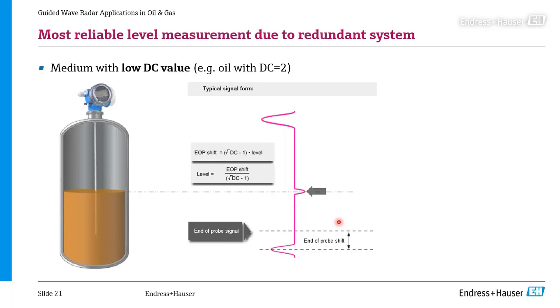Now, this gives me one more thing. This end of probe signal: if you shorten the rod or the rope, you need to tell the unit you did so. Because if you don't, the unit thinks, out of the factory, that the rod has a certain length. So the end of probe signal should be within a certain bandwidth. If you now took, whatever, a foot or 3 feet off, then the end of probe is somewhere else. So you need to tell the unit that you shortened or lengthened the probe. It's only pressing of 2 buttons. Have it determine its own electrical length again. You don't need to go in there with a measurement to determine the length of the probe. It just does it itself, but you need to do it when you make the change, because it will help you get this redundant measurement principle working the right way. Next slide.